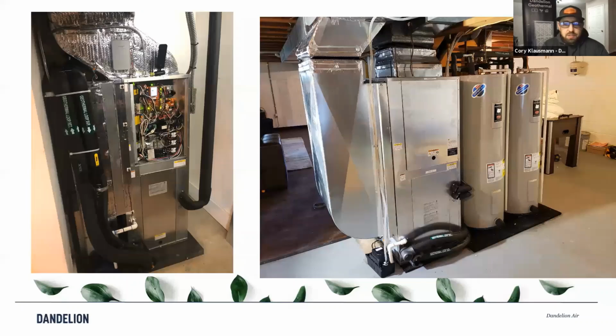We've got two water heaters directly to the right of the unit. The one on the right is our de-superheater, which Keith spoke about. It's not powered by anything — its sole purpose is to capture all the excess heat and energy generated by the system and preheat the water in that tank to around 80 degrees Fahrenheit. You'll get a bit more temperature in summertime because we're pulling heat and humidity out of the house and capturing more heat. Effectively, it should reduce your water heating costs by about a third.